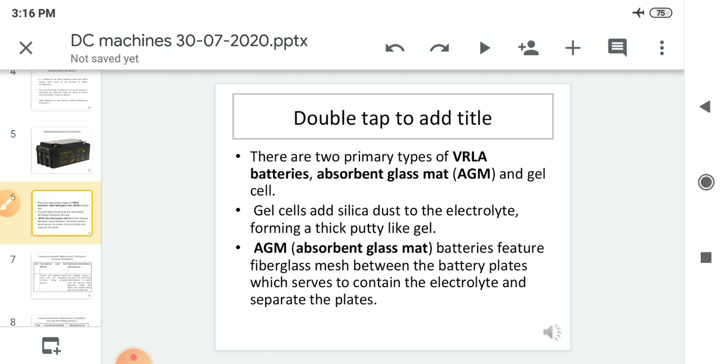There are two primary types of maintenance free batteries. Let's see what gel lead cells are. Gel lead cells means it contains acid that has been gelled by the addition of silica, turning the acid into a solid mass. We are adding silica dust or silica gel. The advantage of this battery is that it is impossible to spill acid even if they are broken.